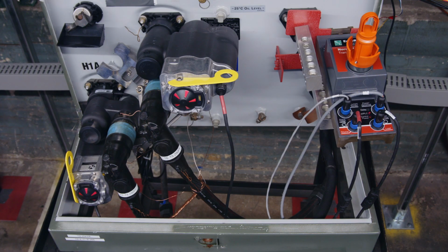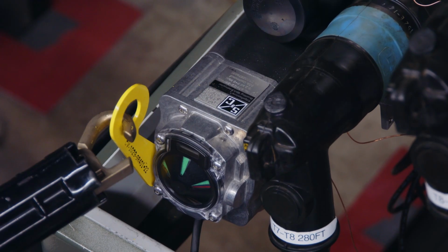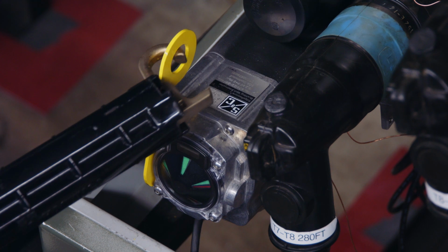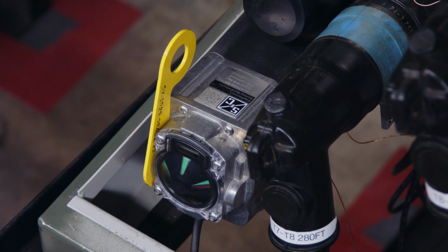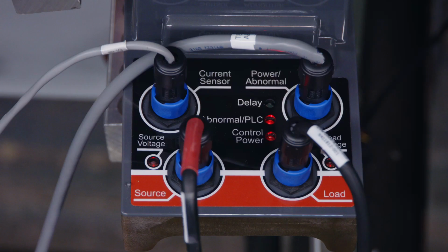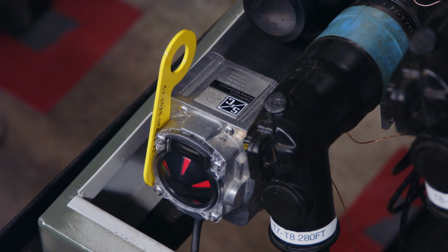Step 6. Open the H1A bushing well interrupter by pulling the yellow lever forward once. Step 7. Close the H1A bushing well interrupter by toggling the handle from the open, green, and locked position to the ready position 3 times, ending in the ready position. Step 8. Make sure the delay LED is blinking. It will blink 10 times and then the bushing well interrupter will close. Step 9. Make sure the indicator on the bushing well interrupter is in the closed, red, and ready position.